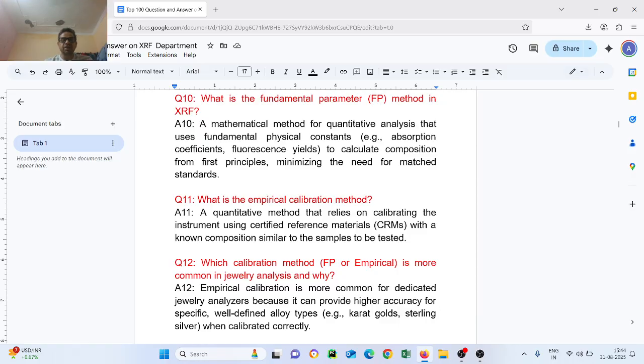Question number 12: which calibration method, FP or empirical, is more common in jewelry analysis and why? Empirical calibration is more common for dedicated jewelry analyzers because it can provide higher accuracy for specific well-defined alloy types, carat gold, sterling silver, when calibrated correctly.